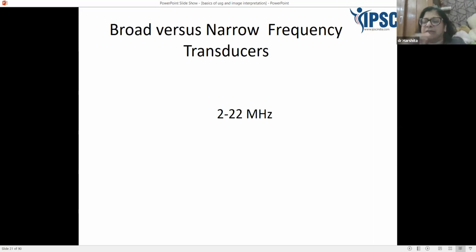Are you a rheumatologist? If you are a rheumatologist, you will always need to do interventions in the little joints of the fingers. So you need a very high frequency probe, maybe a 22 megahertz probe. But if you want to do spine mainly, then you need a low frequency probe. And if you want to do a mixture of everything, then you need a multiple frequency probe. That is, you need a high frequency probe as well as a low frequency probe.